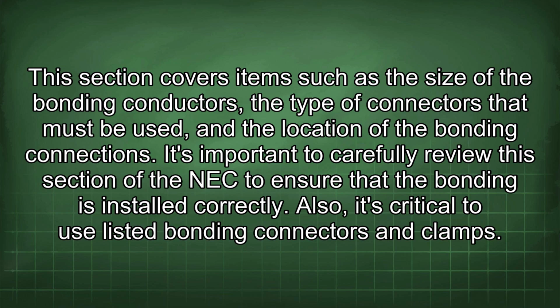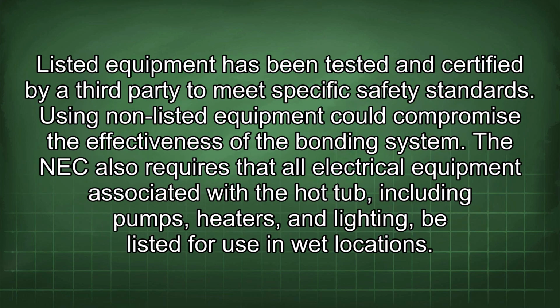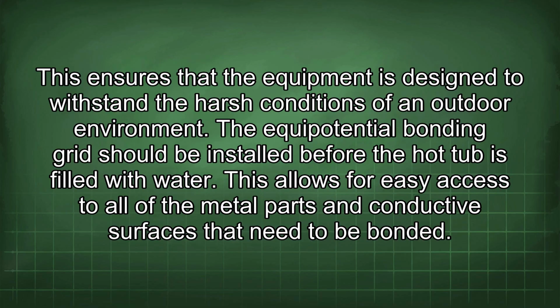Also, it's critical to use listed bonding connectors and clamps. Listed equipment has been tested and certified by a third party to meet specific safety standards. Using non-listed equipment could compromise the effectiveness of the bonding system. The NEC also requires that all electrical equipment associated with the hot tub, including pumps, heaters, and lighting, be listed for use in wet locations. This ensures that the equipment is designed to withstand the harsh conditions of an outdoor environment.